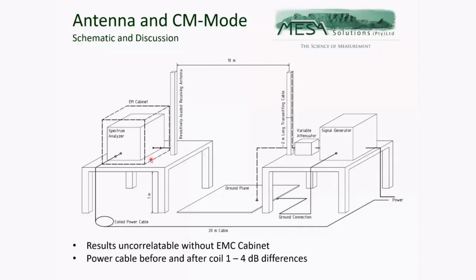But when I first did this experiment with postgraduate students, I didn't use an EMC cabinet, and the results were completely uncorrelatable. I could not show that 5 microamps of current on a resonant cable at say 50 or 60 megahertz caused 37 dB microvolts per meter of electric field at 10 meters distance, which is the limit for most CISPR standards.